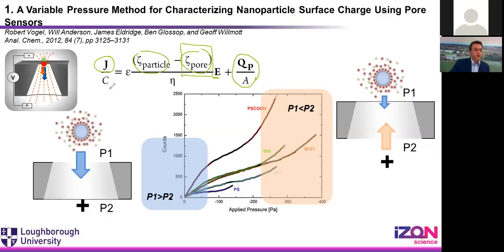So in our experimental setup, we would usually add the particles at the top, so I'm going to start down here in the bottom left-hand corner. Typically, the particles in an experiment would flow from the upper fluid cell to the lower fluid cell, and you would see your pulses. In the graph that I've got here, I've got applied pressure along the x-axis, and it starts at 0, and I've got counts on the y-axis. So with 0 applied pressure, you've got the particles going from the top to bottom, and you have a particle count rate. And you know from the variable pressure module that you can increase the applied pressure in P1 and you increase the particle count.